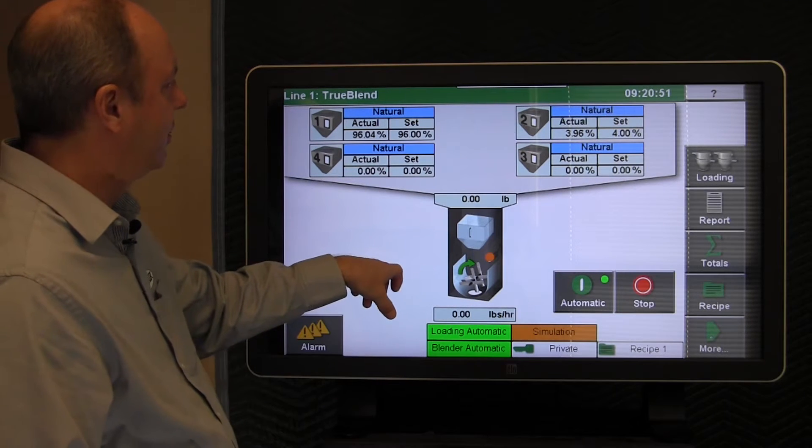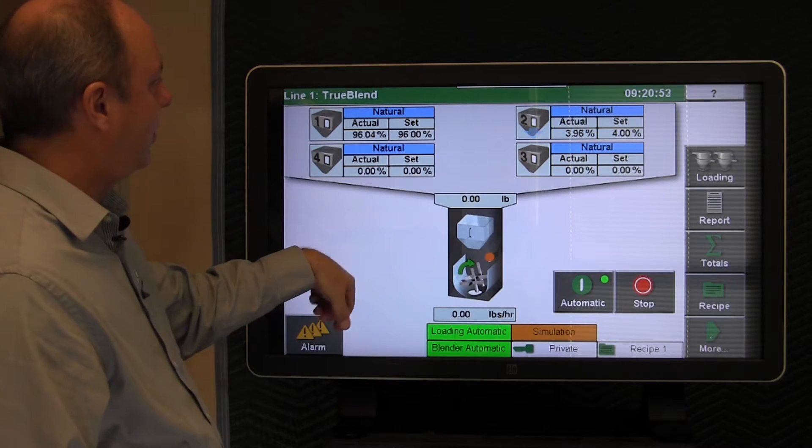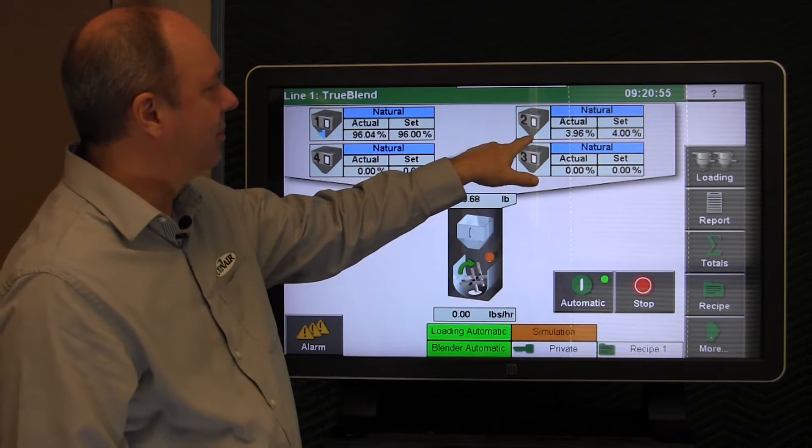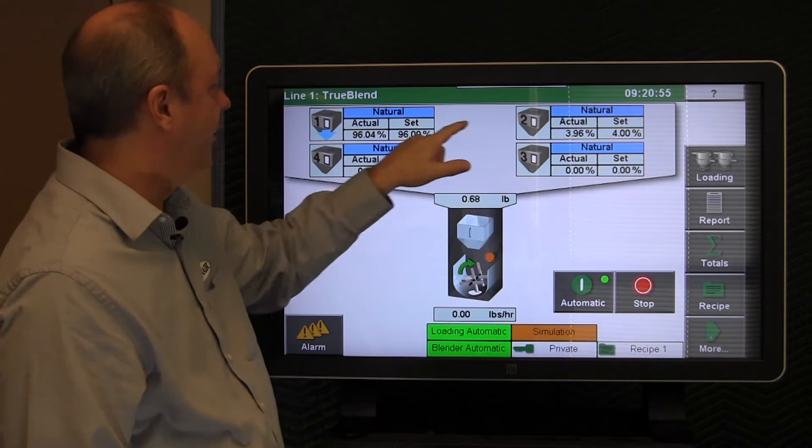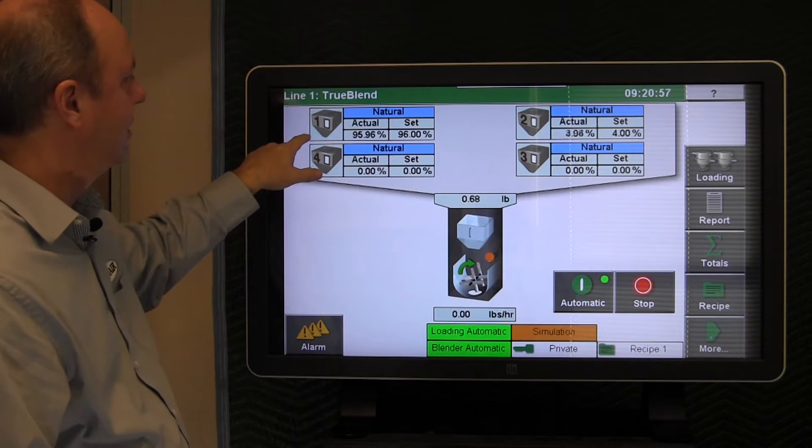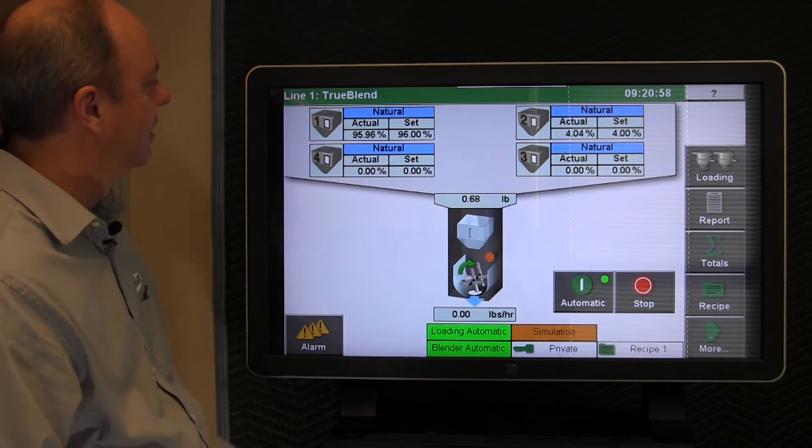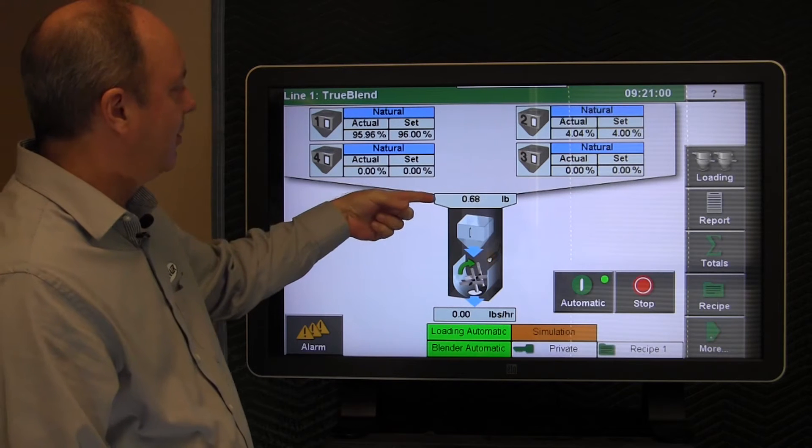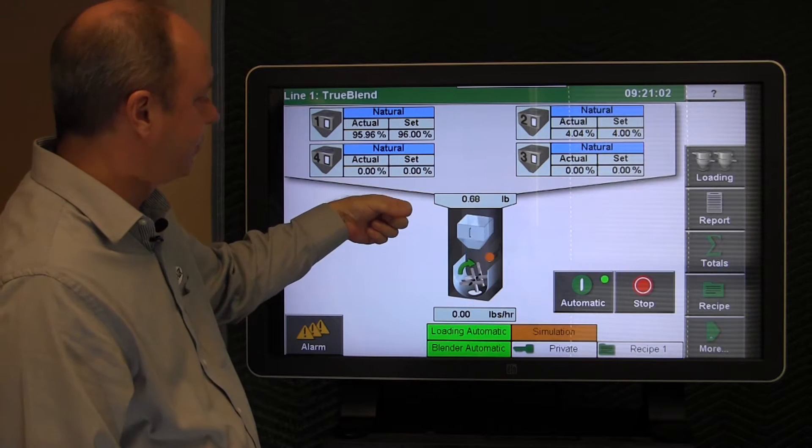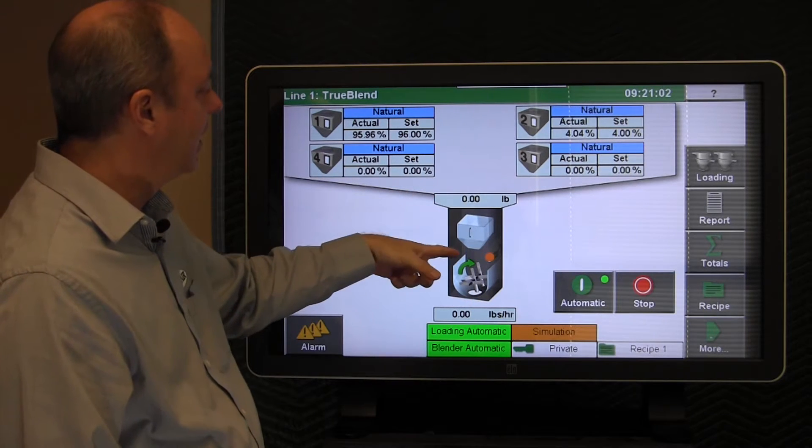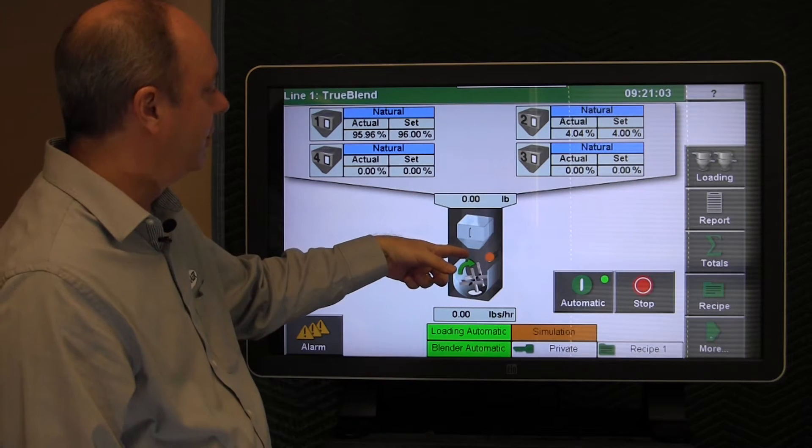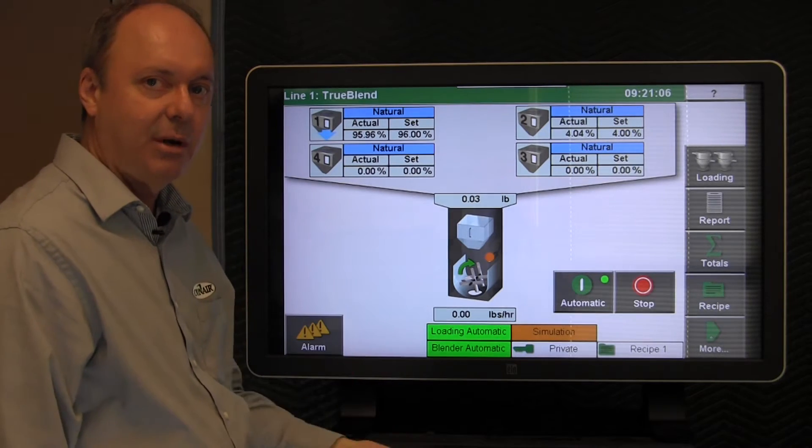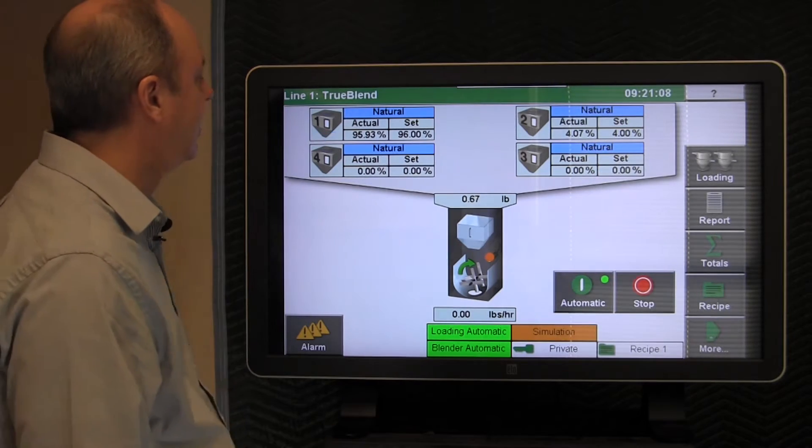Let's return to the home screen and we can watch the performance of the blender. The arrows pop up on the screen when things are occurring. You can see it doses the minor ingredient first, it doses the major ingredient next. This is how much material is in the batch hopper. The arrow that appears at the bottom of the batch hopper indicates that the batch hopper is actually dumping out.